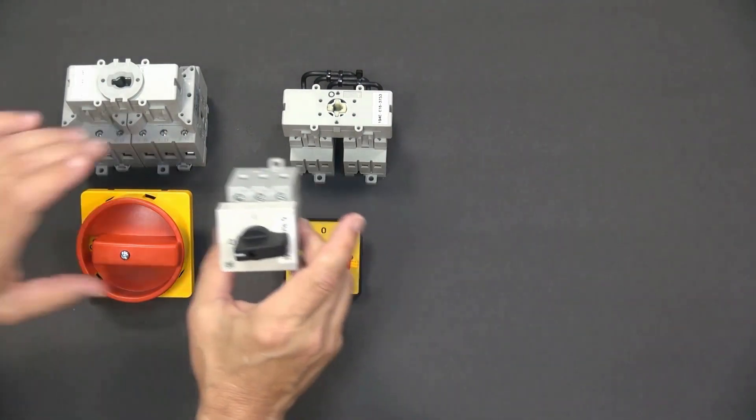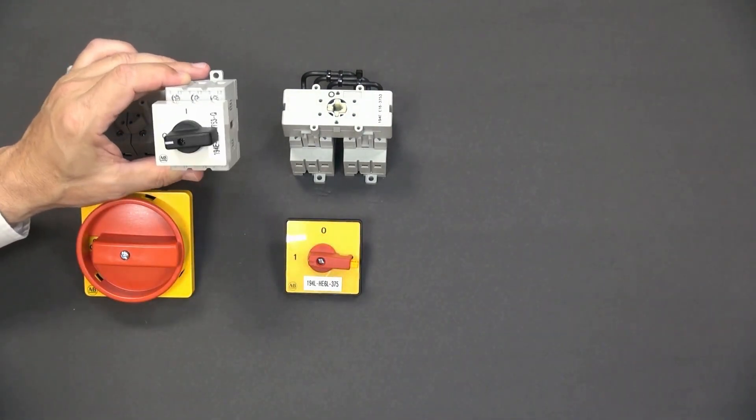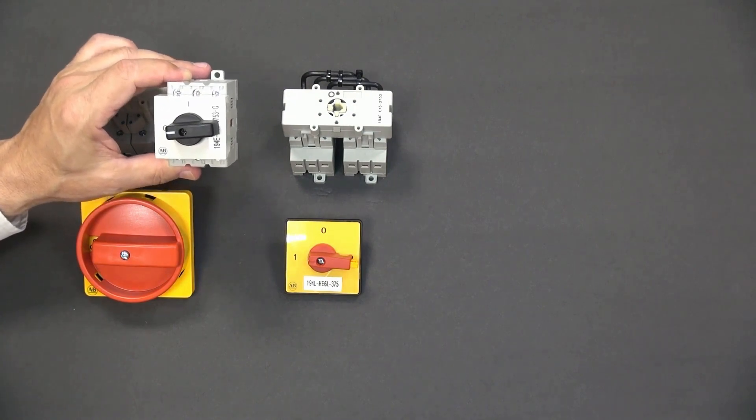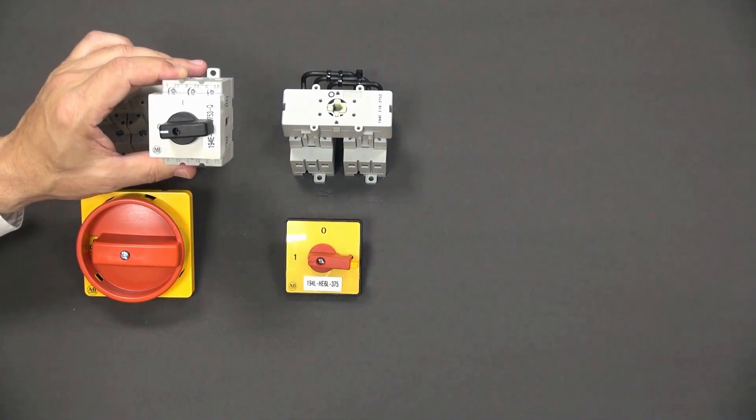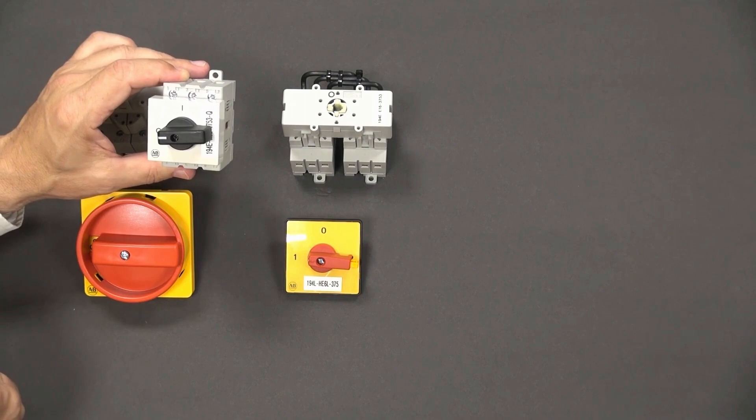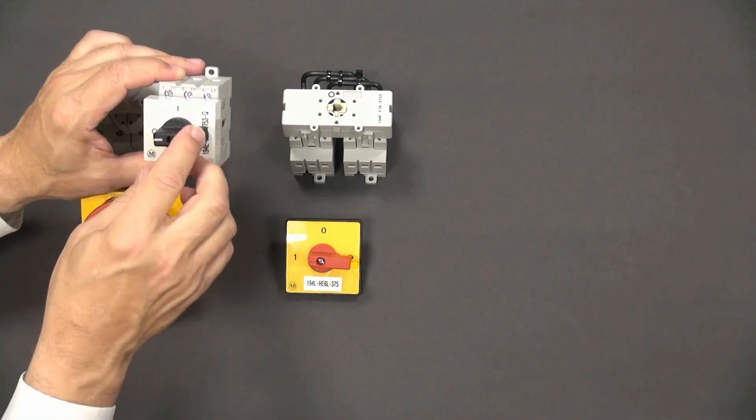This little switch is a 16 amp panel mounted base switch with a door or face mounted handle. This little switch has application inside the control panel and is typically fitted with terminal covers. Many industrial installations require a maintained source of control power and are not connected through the three-phase disconnect.